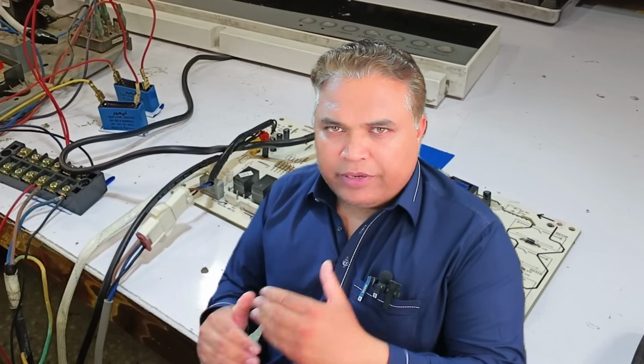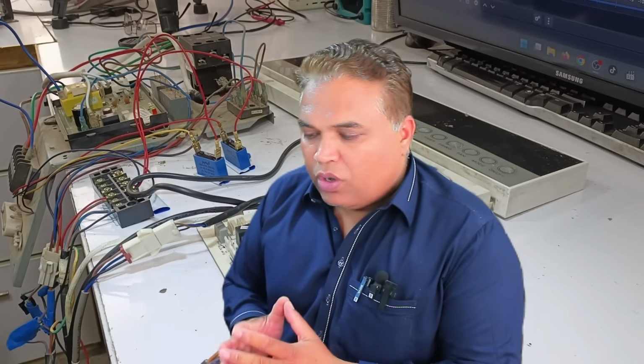It operates using a 3-phase power supply, as I have already explained to you earlier. There is one circuit board in the indoor unit and another circuit board in the outdoor unit. Both boards have separate responsibilities, and I will explain that to you. The indoor unit does not directly communicate with the outdoor unit in any way. What happens is that the outdoor unit sends a signal that the indoor circuit board receives. How that signal is received, we will discuss that a little later. But for now, let me show you where it is received.